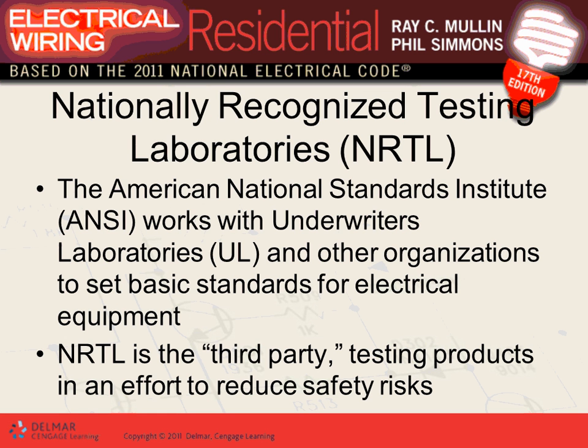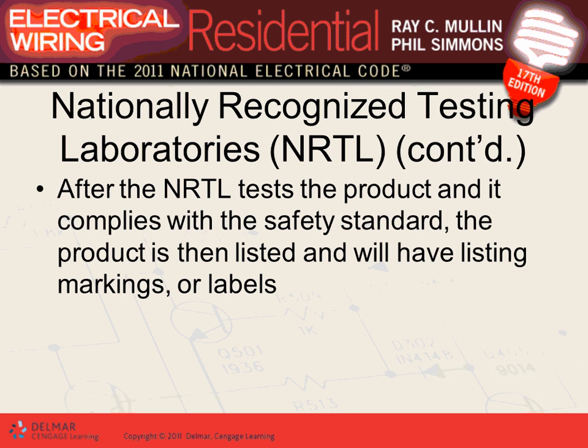That's the Nationally Recognized Testing Laboratory, a big deal. UL is one of the most famous. It's third-party verification: they take the equipment into their factories, pump voltages and current into them, and see if it can handle the specification from the manufacturer. So if it's rated 4,000 amps, they put 4,000 amps into the switchgear and watch it. The spec says it should handle 4,000 amps for 30 cycles, which is half a second. If it doesn't blow up within that half second, check, done. If it blows up sooner, it fails, and they send it back to be redesigned. It's a big deal.